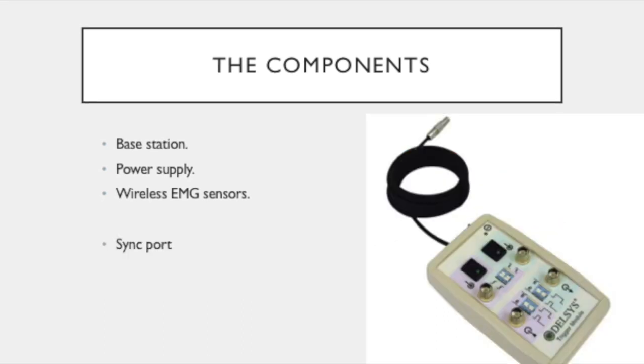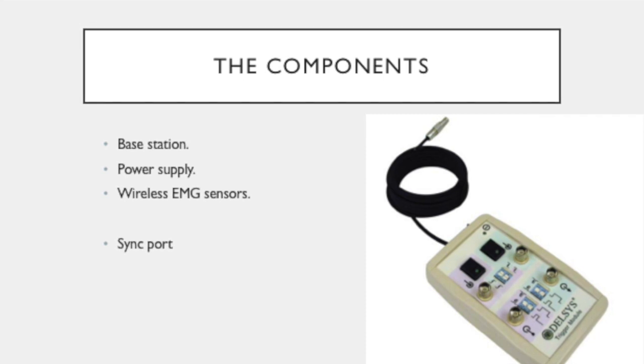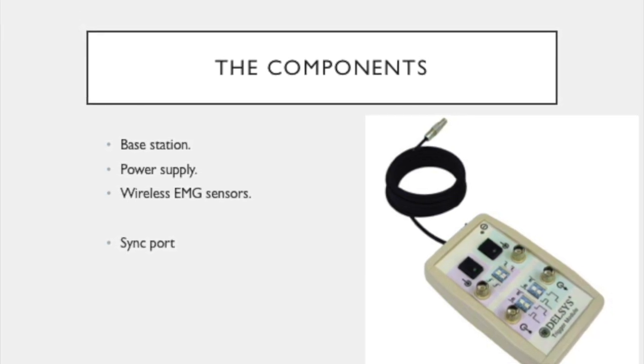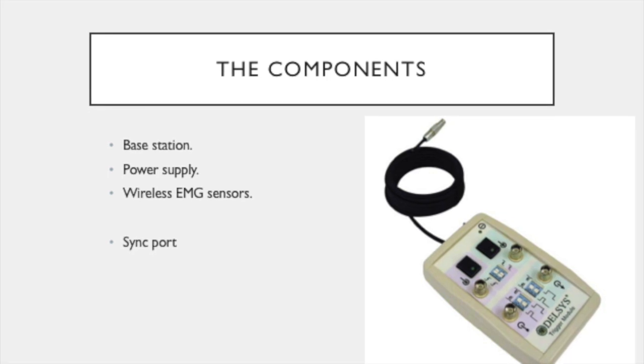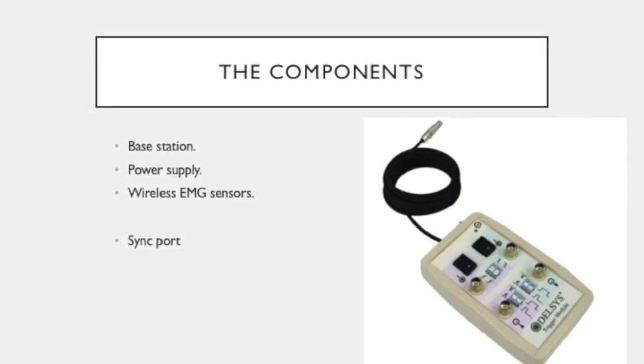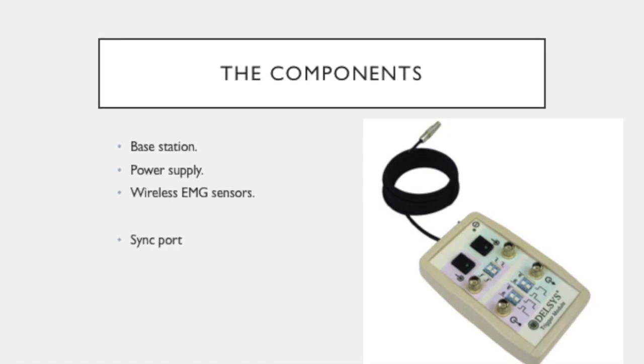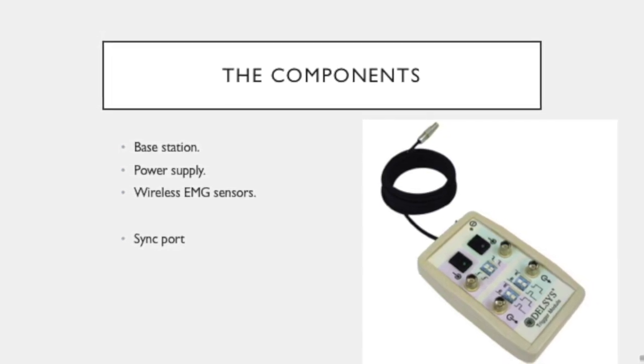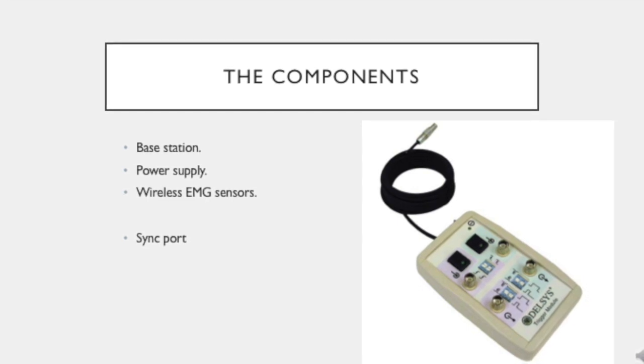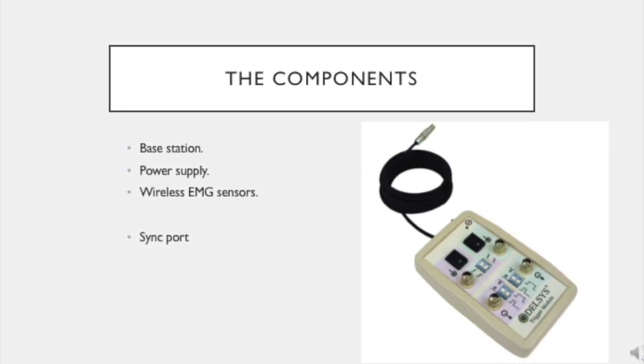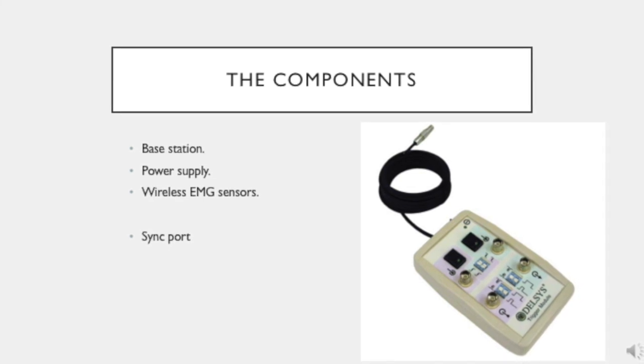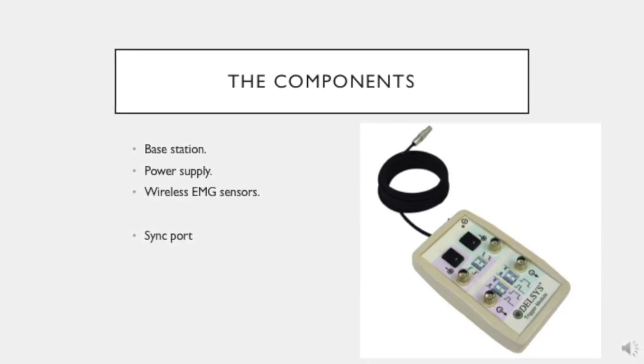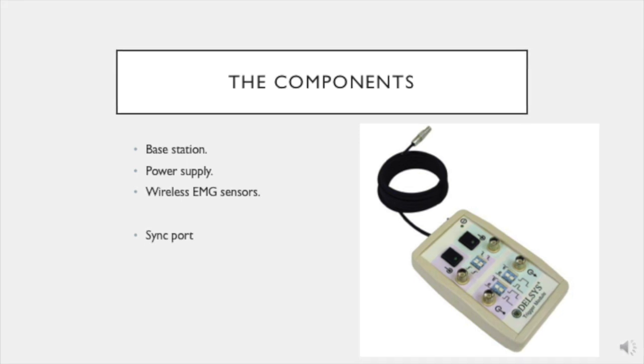Lastly, there is the sync port. In addition to the DELSYS-Trigno system, it is also necessary to have a sync port. The sync port serves to synchronize the data from the DELSYS-Trigno wireless EMG with data from the Vicon system. The sync port ensures that the timing of EMG events can be matched with the timing of data from the Vicon system, such as motion capture recordings and force traces. Our setup utilizes the DELSYS-Trigger module as a sync port.